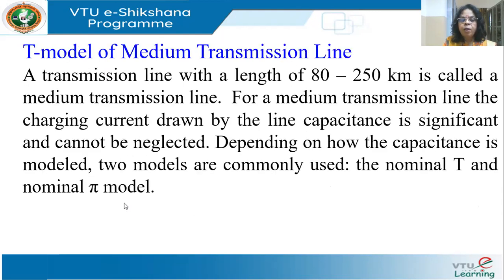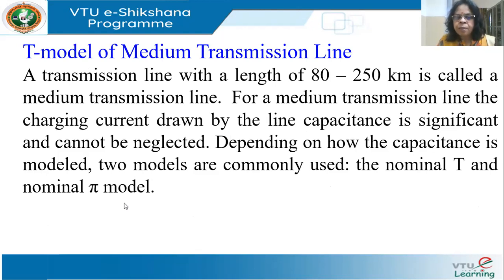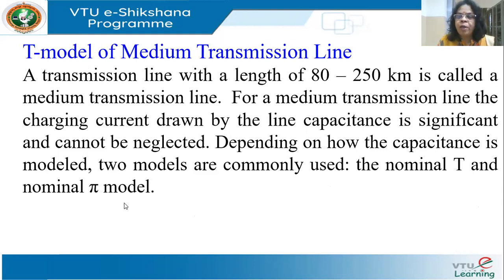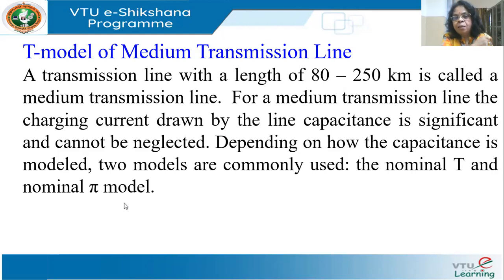Next, let us move on to the T model of medium transmission lines. The T model is one of two popular models for medium lines. Medium lines are normally between 80 or 100 to 250 kilometers. For this length, you cannot afford to neglect capacitance. If we neglect capacitance, we cannot account for the Ferranti effect or know how much the receiving end voltage will rise under light load conditions. So the capacitor has to be modeled. Based on how we model resistance, inductance, and capacitance, there are two popular models: the nominal T and the nominal pi models.